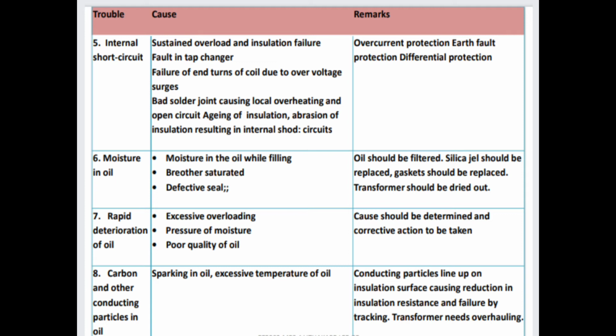Then the sixth is moisture in oil. When there is moisture in oil, what are the causes? Moisture in the oil while filling, breather saturated, defective seal. And remarks are, oil should be filtered, silica gel should be replaced, gasket should be replaced, transformer should be dried out. Next, rapid deterioration of oil. Causes are excessive overloading, presence of moisture, poor quality of oil. Remark is, cause should be determined and corrective action taken.